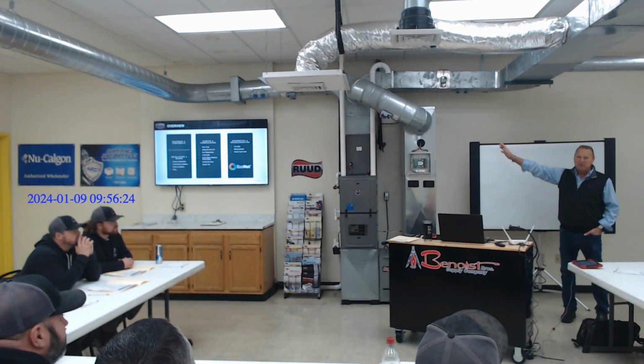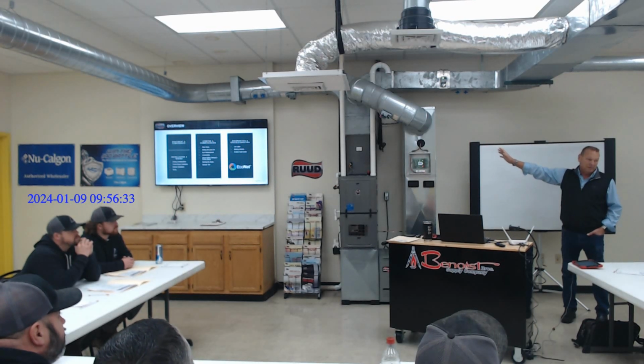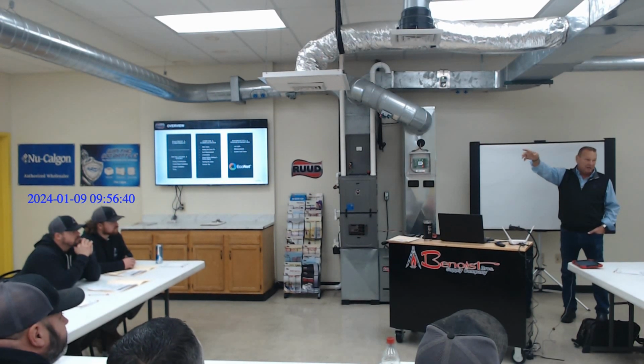Most of our problems in the field are undersized returns and oversized equipment, right? We walk in, we sell a job, we don't do a load calc, we oversize the furnace, and we're screwed. I don't care if it's zoned or not zoned, because of how these motors actually work. Back in the day, these ECMs burnt that little black disc up that was a limiter. That was because they were running too high static pressure. None of us ever really realized that.